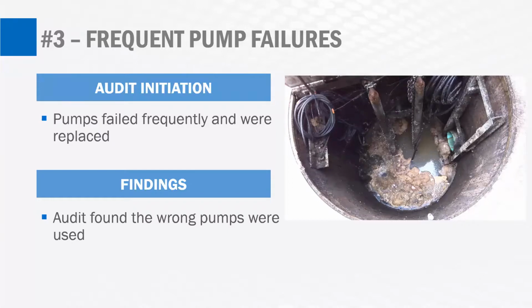So what the audit team had to do is go back and start digging through a lot of the design data and really try to figure out what was going on here. It turns out that the pumps weren't ideally suited for this situation. On paper, everything looked great. Everything looked like it should be performing as well as it should be. But when we did a detailed hydraulic analysis on this station, we found that the pumps were operating far, far to the right on the curve.